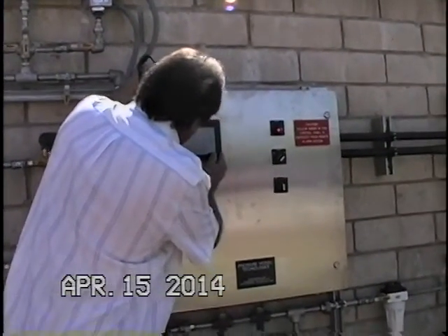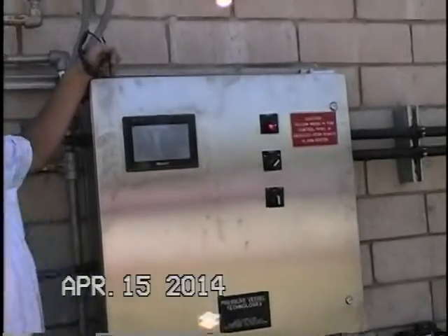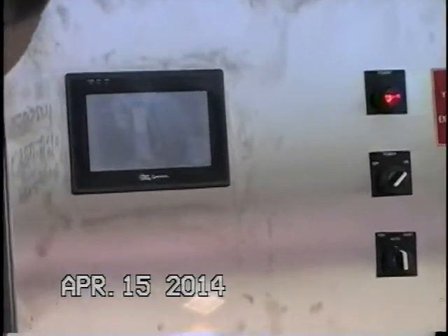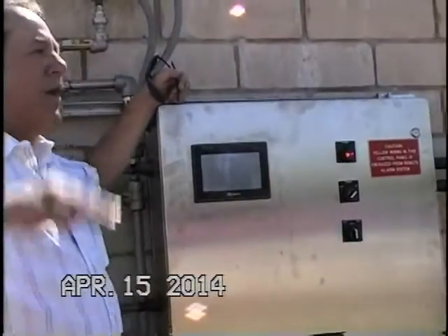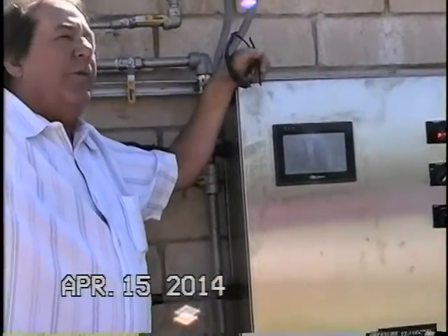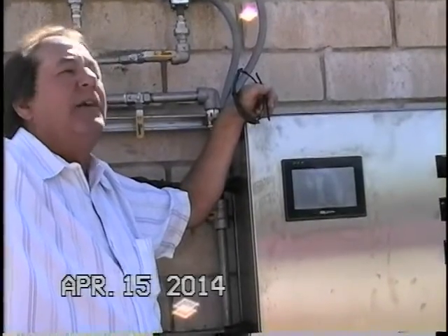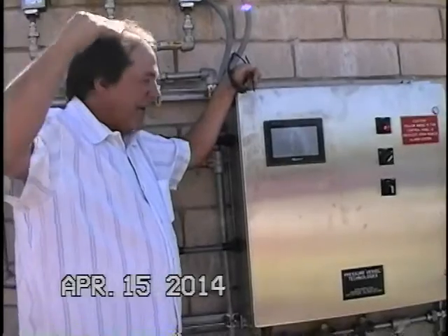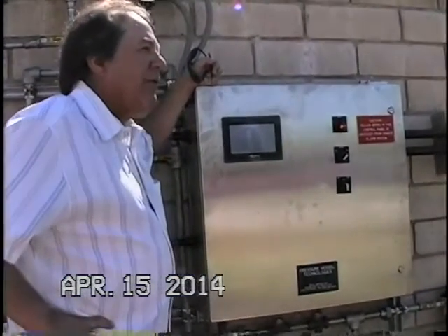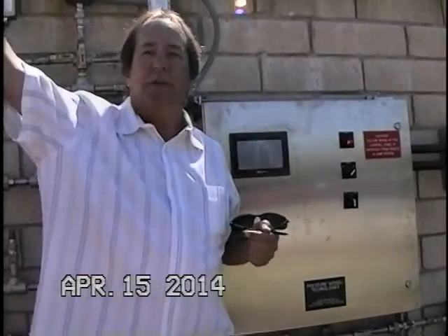Now, the other screen that you had talked about was the alarm set points. That sets your high level and low level alarms, very similar to your add air and vent air screen. Currently we've got it set at 54 inches and 39 inches. So basically 6 inches above our 48, and 3 inches above our add air at 51. If we fail to add air and that liquid level continues to rise, then you're going to get a high level or a low level alarm, and that's a direct output to SCADA.